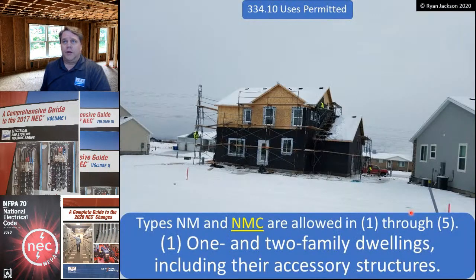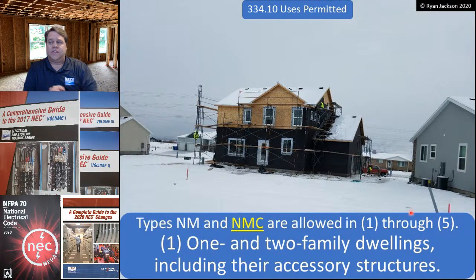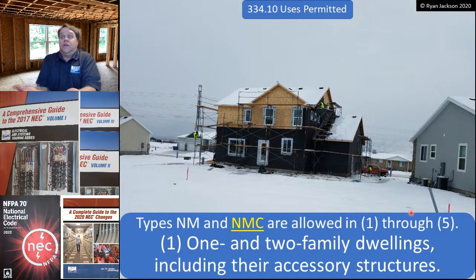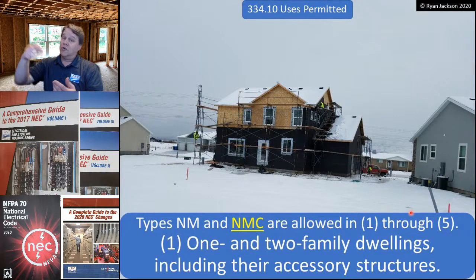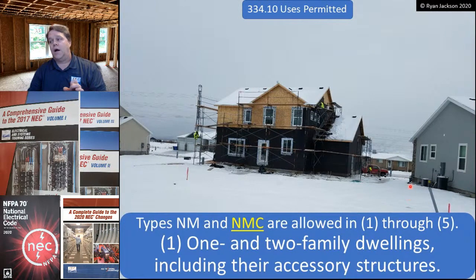Let's get into uses permitted. Article 334's uses permitted has a lot more teeth than most uses permitted. As a matter of fact, a lot of the uses permitted sections, the .10 sections of Chapter 3, have an informational note saying, hey man, this isn't a list of everything, we can't tell you everything you can do with the cable. But with 334, we kind of do. We're pretty specific. You can use it here, here, here, here, and here. And then as we're going to find out when we get to the uses not permitted, it kind of says, hey, go back and read uses permitted once again. So the uses permitted for Article 334 is a lot more robust and a lot more meaningful than some of the other uses permitted.